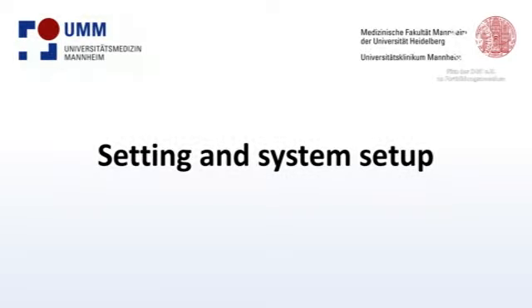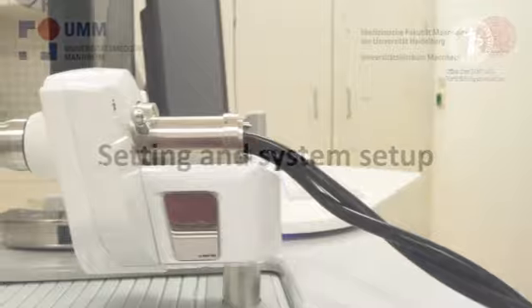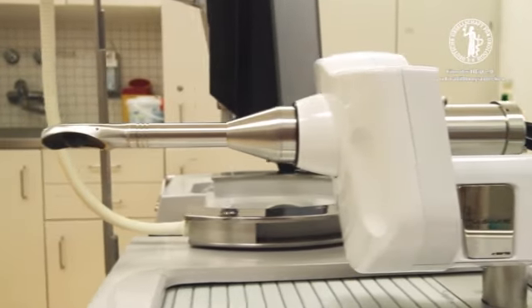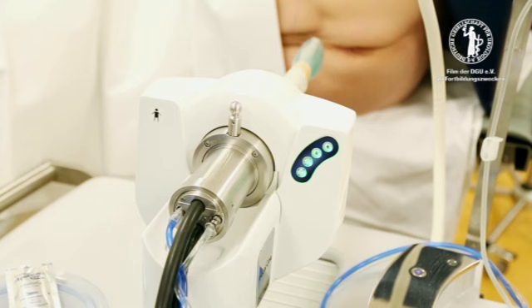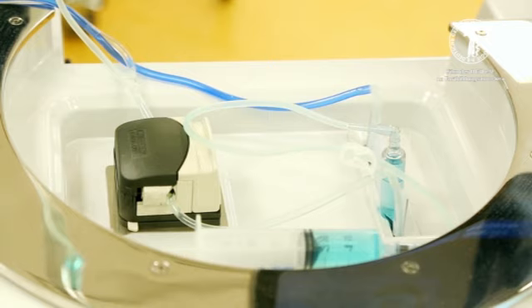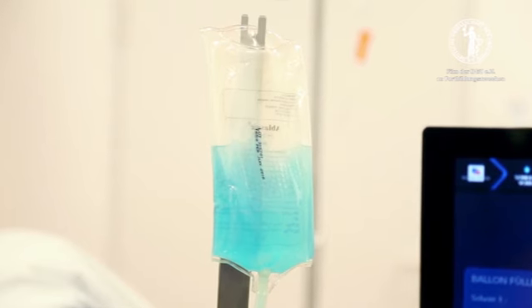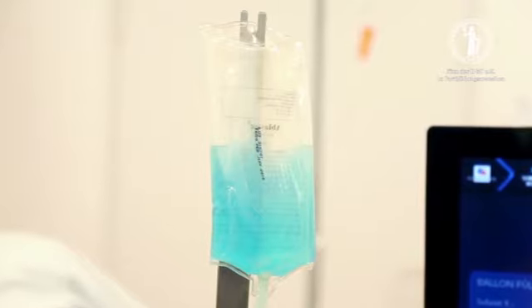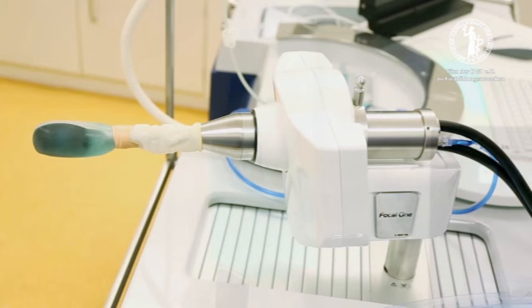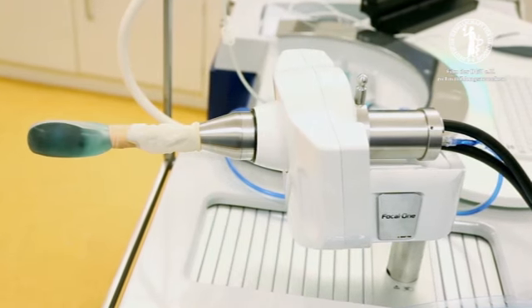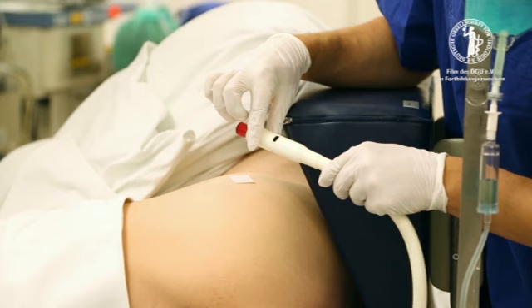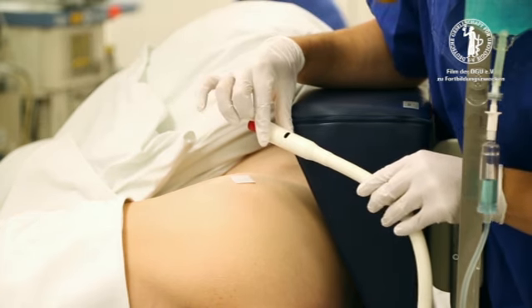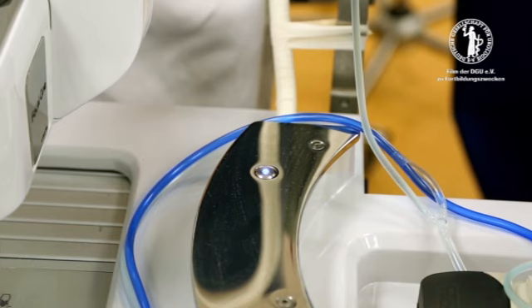The combined imaging and therapy probe is placed on a robotic platform. Piezoelectric elements in the spherical transducer of the probe enable the generation of 3 MHz acoustic waves for heat ablation. Cooled coupling liquid flows continuously through the latex balloon to protect the rectal wall and adjacent structures. Using a temperature detector, we are able to maintain a constant temperature. A light barrier immediately detects patient movement and automatically stops the treatment during the ablation. A restart with replanning of the lesion might be necessary in such cases.